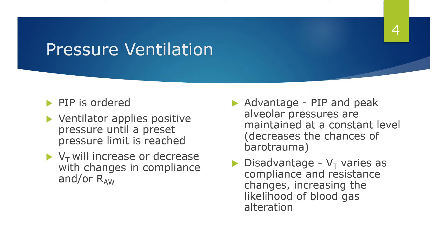In pressure ventilation, the peak inspiratory pressure is ordered by the physician and set on the ventilator. In this type of ventilation the peak inspiratory pressure is set and will not change — the ventilator will apply positive pressure until a preset pressure limit is reached. The tidal volume, however, will change: it will increase or decrease with changes in compliance and/or airway resistance.